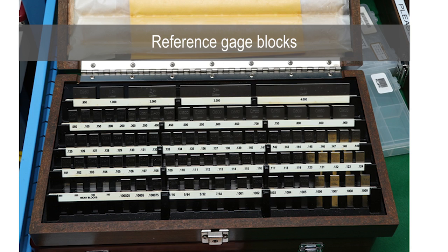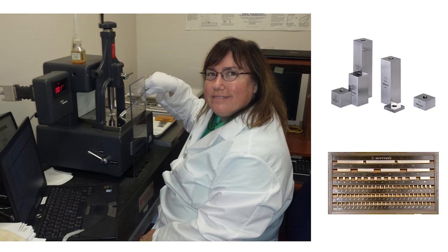Next thing we need to know is what are our reference gauge blocks. What you're looking at is the reference set that was calibrated by NIST. This is as accurate as any calibration lab can have. The way we take advantage of these reference blocks is you then go to the actual measurements. You have a gauge block comparator. So first you put in the reference one that you know the actual value, then you zero the gauge block comparator, and then you put in the one that a customer submitted. And the difference that you see on the reading, that's the error between the two.